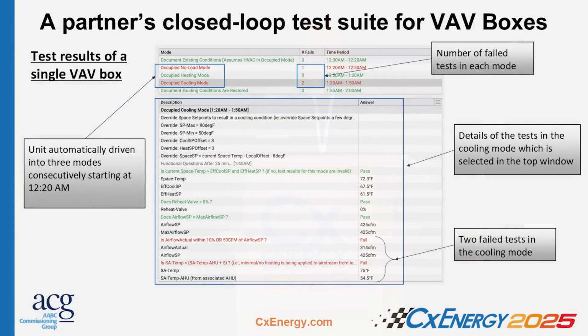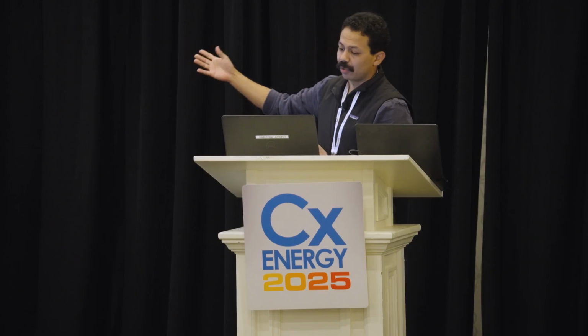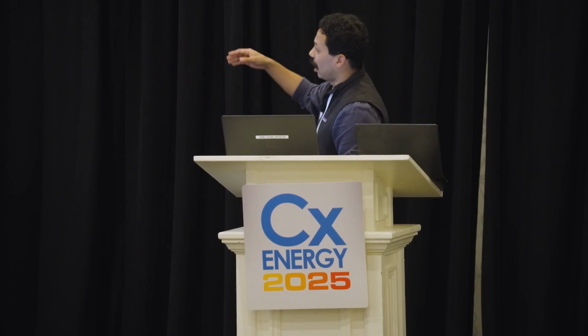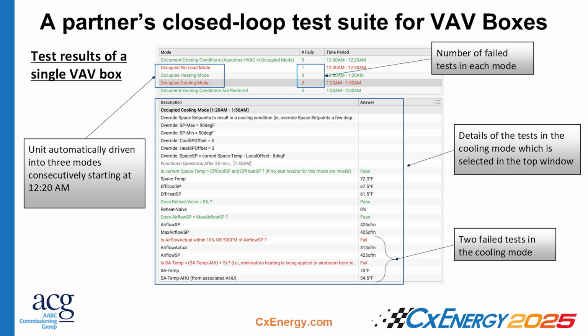And then you drive the set points very high to heating mode. You monitor a whole different set of criteria for that. Specifically in this case, it would be a reheat valve. And then you would have a series of pass-fail criteria for that. So we have a partner doing this as well. This is a closed-loop test suite in their application here. On the left sort of box here, that's pointing to their driving their set point up and down to elicit that mode response. And then on the right sort of block pointing there, you're seeing the FDD rules that are triggered at certain stages of those mode responses as well. In addition to that, they have a report output similar to the last partner, showing green text when it's passed, red text when it's failed.